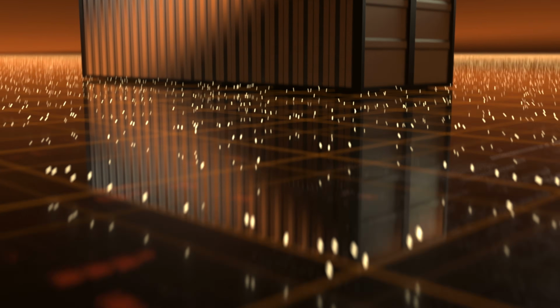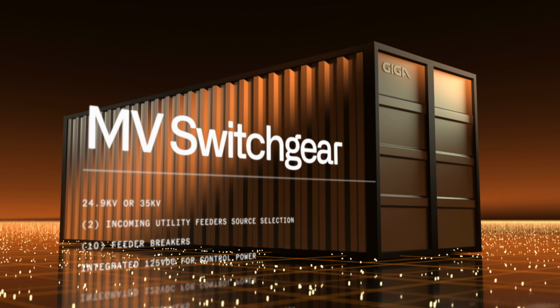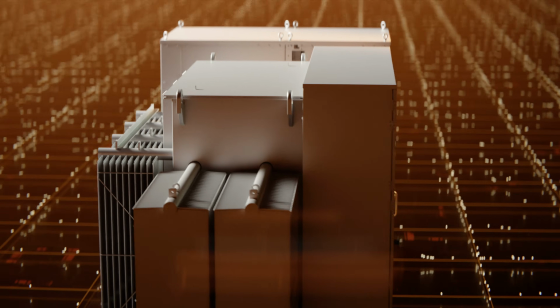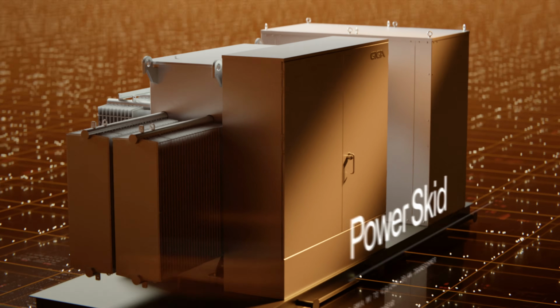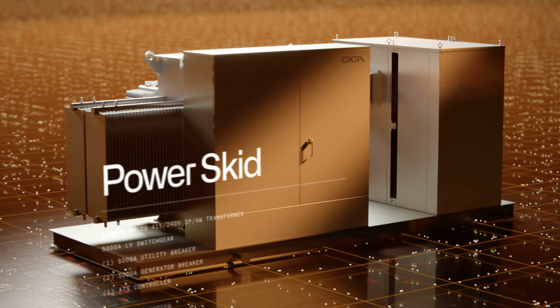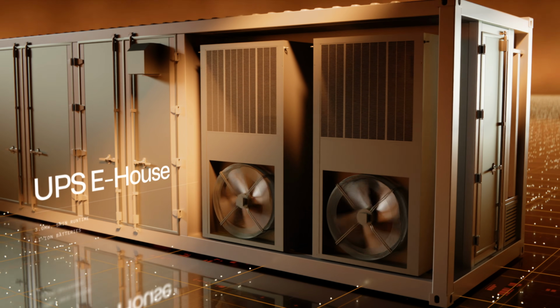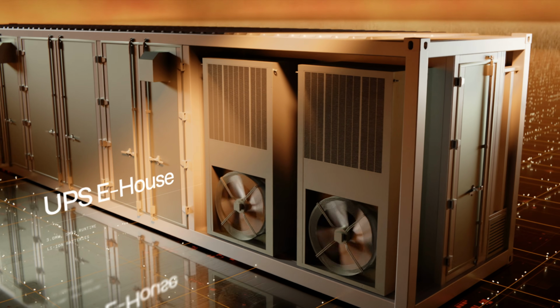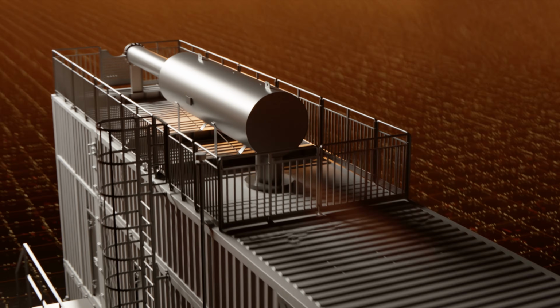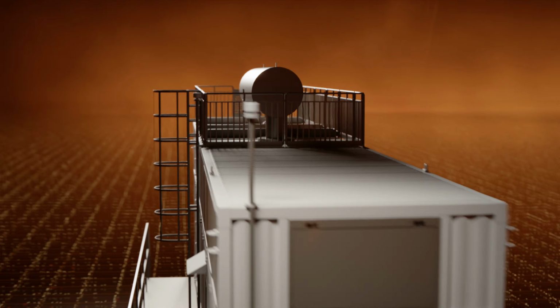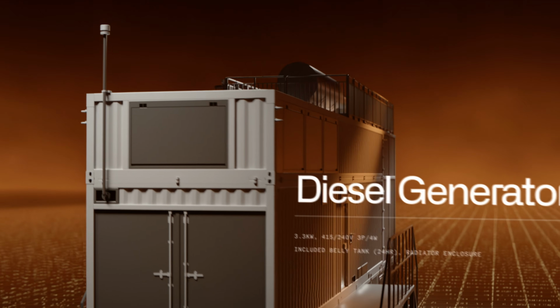The power chain includes medium-voltage switchgear handling utility energy, power skids to step down and deliver voltage, a UPS e-house module with lithium-ion batteries to bridge any utility interruption, and our diesel generator module to ensure power stays stable with no interruptions.